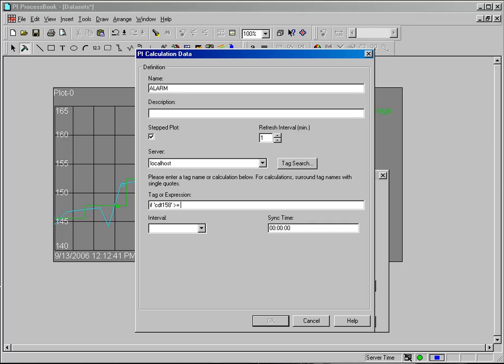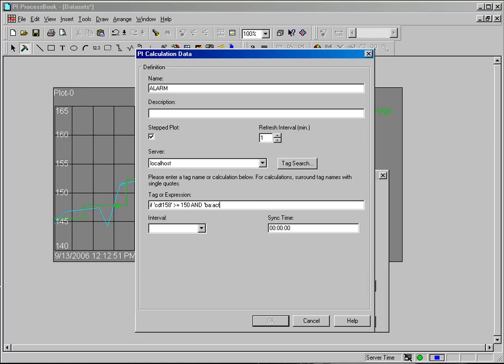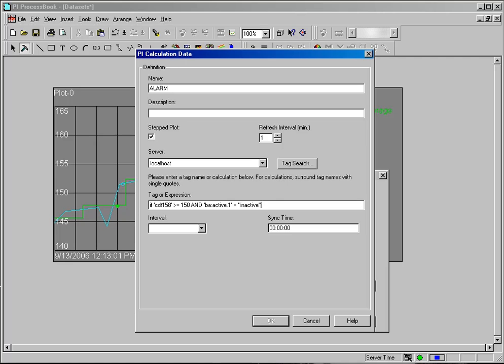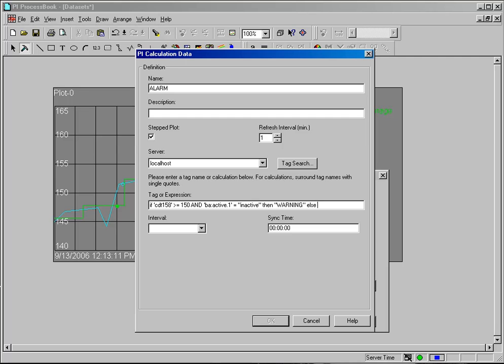Let's say maybe I go over a certain degree and my relief valve is off. So what I can do is create an expression that goes if CDT-158, I remembered my single quotes, is greater than or equal to 150. And I have a tag here called BA colon active dot one. This tag has values of either active or inactive. I will say if that's value is inactive, then I want to produce the message warning. And if we don't meet that criteria in any other condition, I want to report the value of normal.